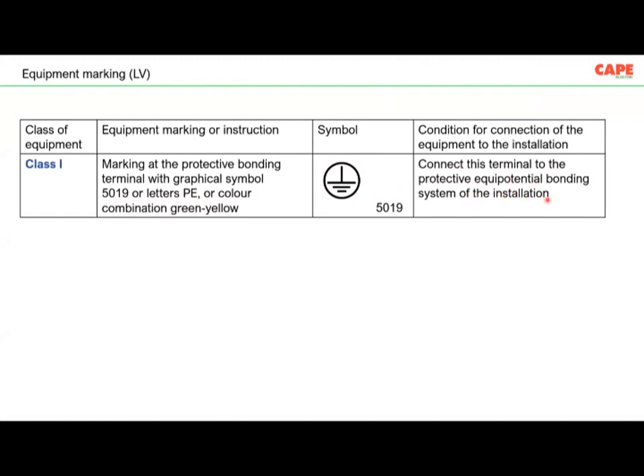That particular equipment, which has this particular marking, must be connected to the protective equipotential bonding of the installation. So earthing the equipment is very simple. You have a terminal in your equipment, you take a wire and connect that equipment to the equipotential bonding system of your installation.